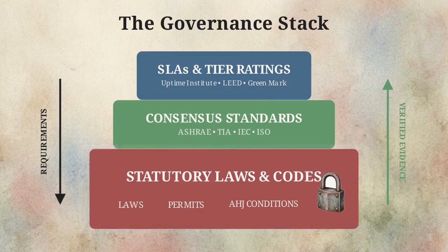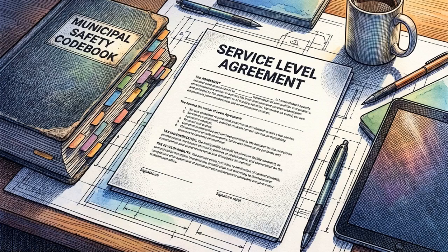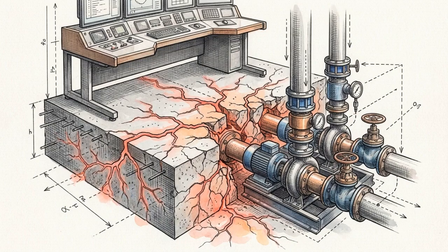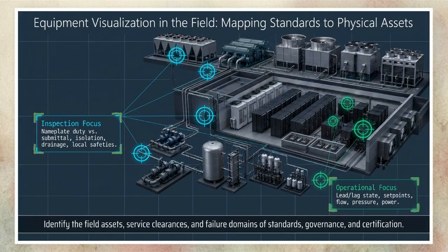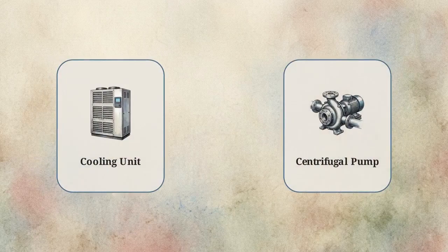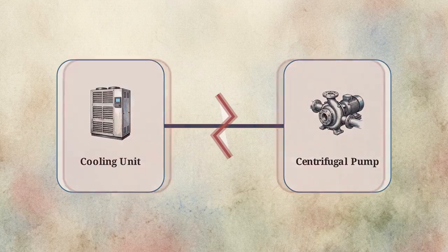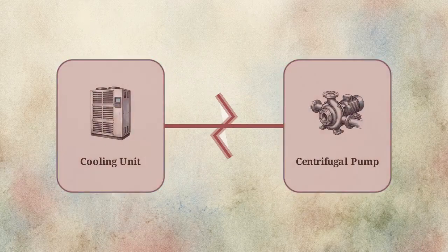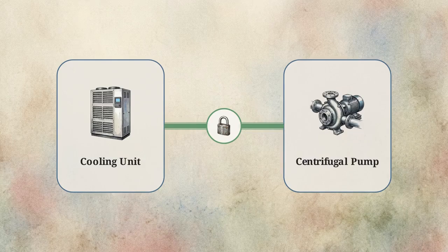The law always wins. Operators frequently prioritize an owner's SLA over local municipal code, assuming the higher standard supersedes the baseline. Doing so creates an immediate legal liability and builds hidden fault lines waiting to cascade through the system during a critical failure. This schematic highlights the specific operational and inspection boundaries across a chilled water plant and server floor. Cascading mechanical failures rarely happen in the center of an isolated asset. They occur at the seams between independent systems, requiring strict interface ownership to prevent a system collapse.